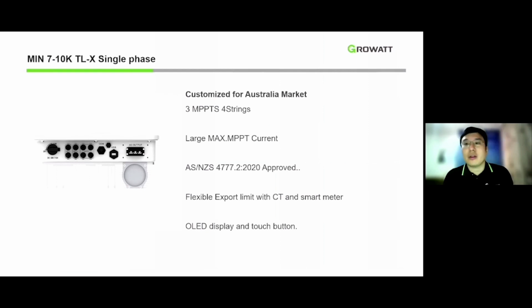I understand some large single phase inverters in the market also have 3 MPPTs, but only 3 strings. Ours has 4 strings, making it easier for end users and installers to get their full 1.33 times STC. Also, the DC current is as high as 13.5A, so it can easily handle 400 and 500 watt panels. It's AS4777 2020 approved.